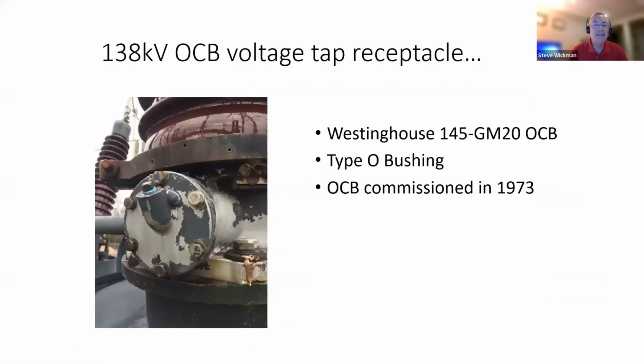We got invited to take a look at a situation here. This is a 138 kV oil circuit breaker, 1973 vintage, and the voltage tap receptacle was starting to leak. And notice the old clamp that's on that interface area above that voltage tap. Judging from the condition of that clamp, that was put on quite a while ago, and that's still effectively doing its job too.